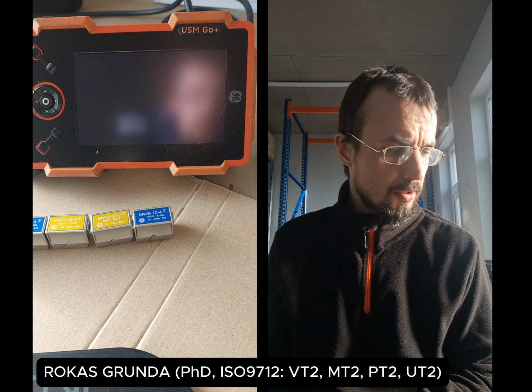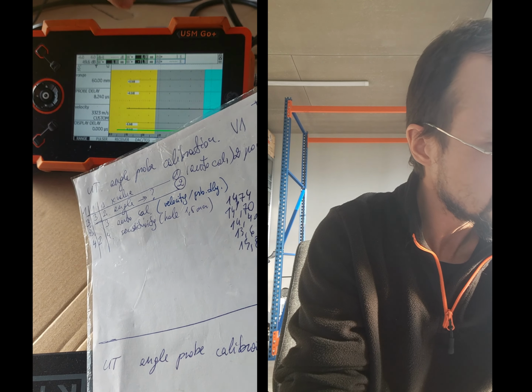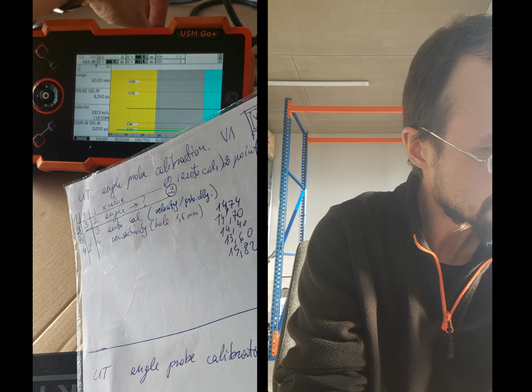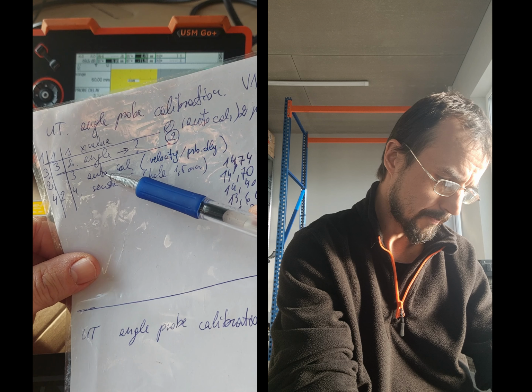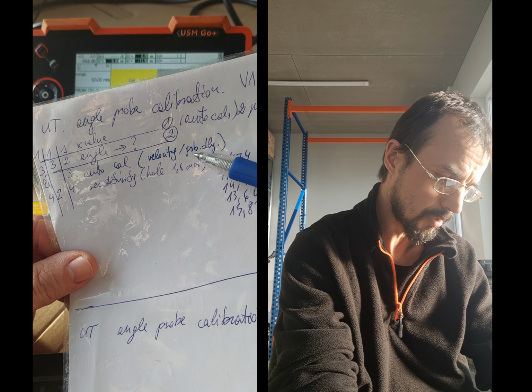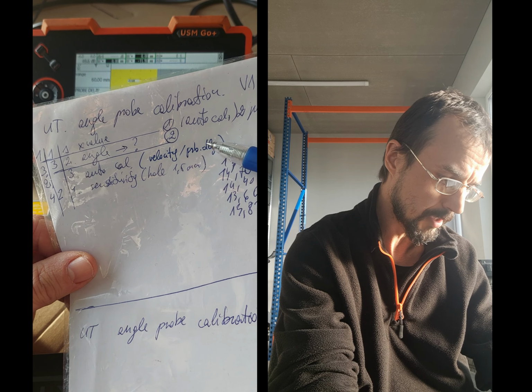Next, what I will be doing is this. Angle probe calibration with first block. Checking the X value of the probe. We'll be doing 3, 70, 60, 45. So each of the videos will be about each of them. Checking the angle, then calibrating velocity with probe delay or only probe delay. We need to check this. Sensitivity hole on the first calibration block. And when we go to the normal probe, here is what we'll do. Check vertical linearity, check resolution, sensitivity, and things like that. So that will be later. We'll do angle probes first.